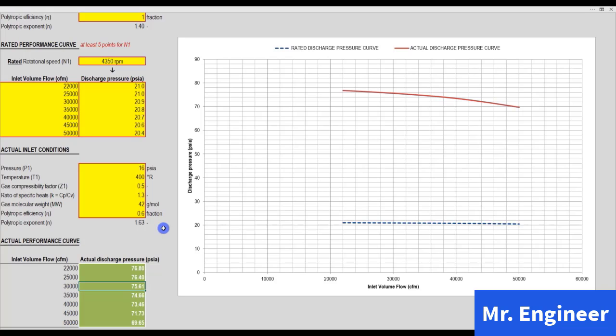Now, since compressor manufacturers will not normally supply performance curves for other than rated inlet conditions, then it becomes extremely important for you to know how to account for your process condition changes by modifying the performance curve of your compressor. This will help you better operate your centrifugal compressor and know if it is performing its duty correctly. You can use this methodology to modify your compressor discharge pressure performance curve for any type of gas and for multi-stage centrifugal compressors.